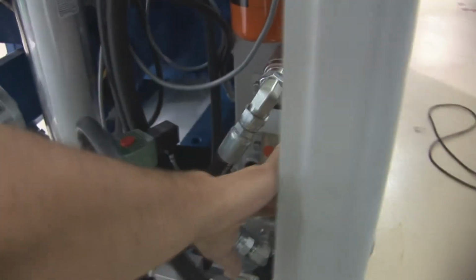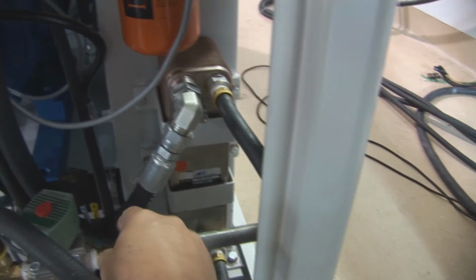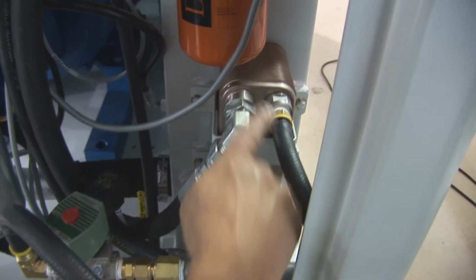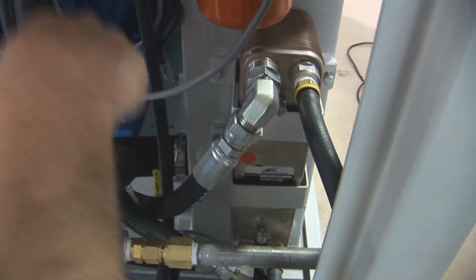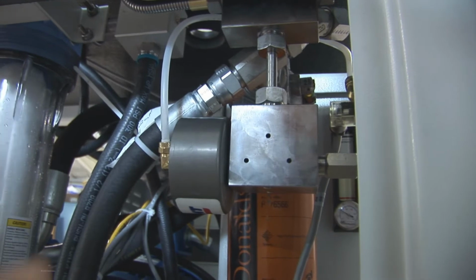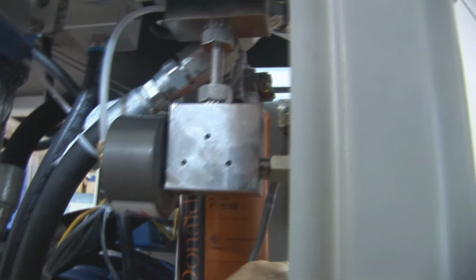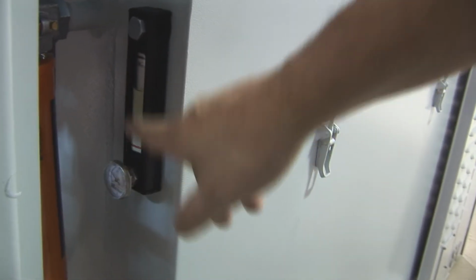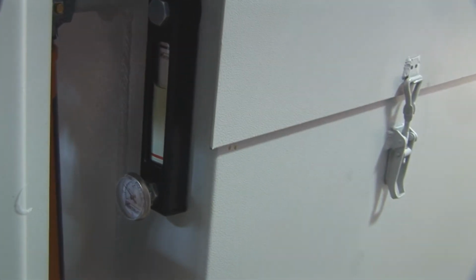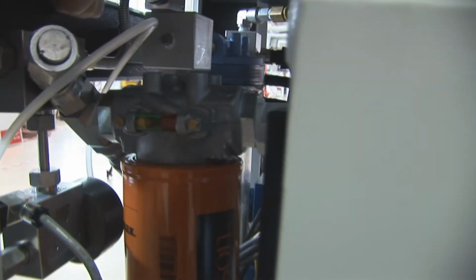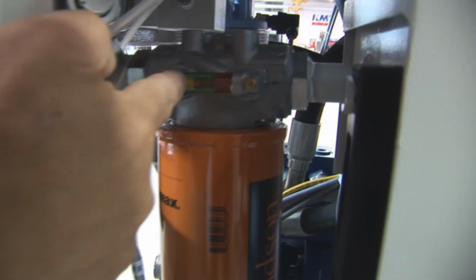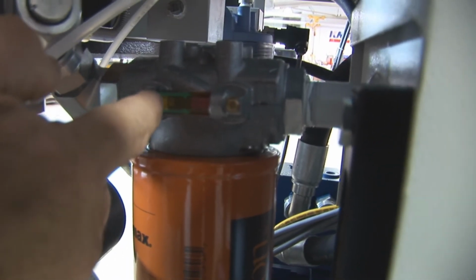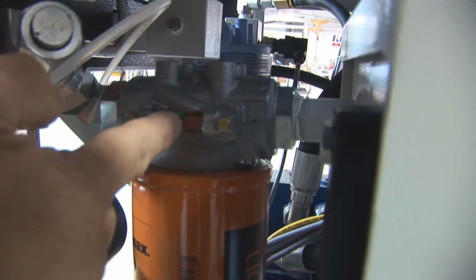That's the water side. The oil side, the oil comes in from your recirc pump through the heat exchanger up to the filter assembly, and from the filter assembly it goes back in the reservoir. On your reservoir you have a temperature gauge. You read the oil temperature here and the oil level there. You want to keep it between the red and the black, somewhere in between. On the oil filter, we have an indicator up here, a little yellow plunger. When it gets over into the red, that's indication you need to change your filter.